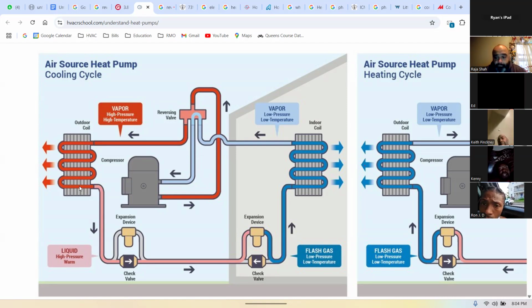Whatever pressure you're getting on the actual gauges will tell you exactly... well, there's another point of information that we look to: the saturation temperature on the gauge itself, or your subcooling.